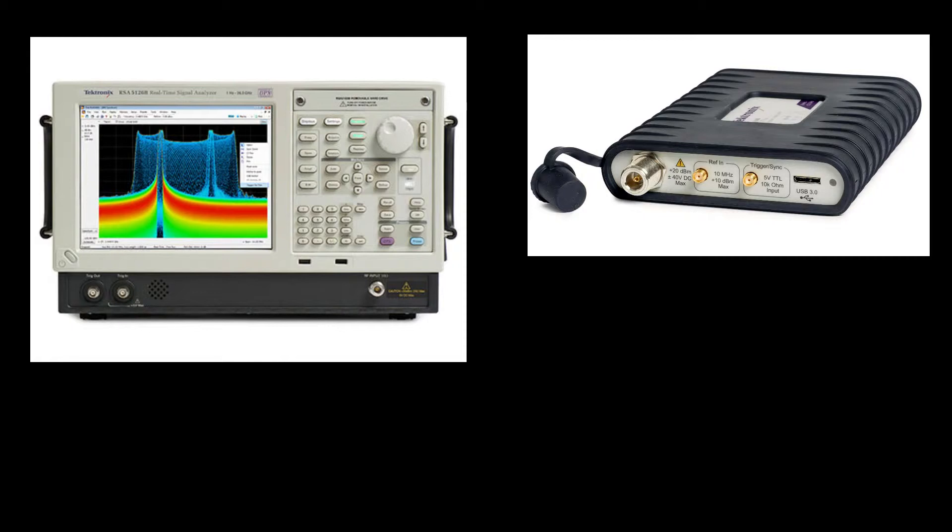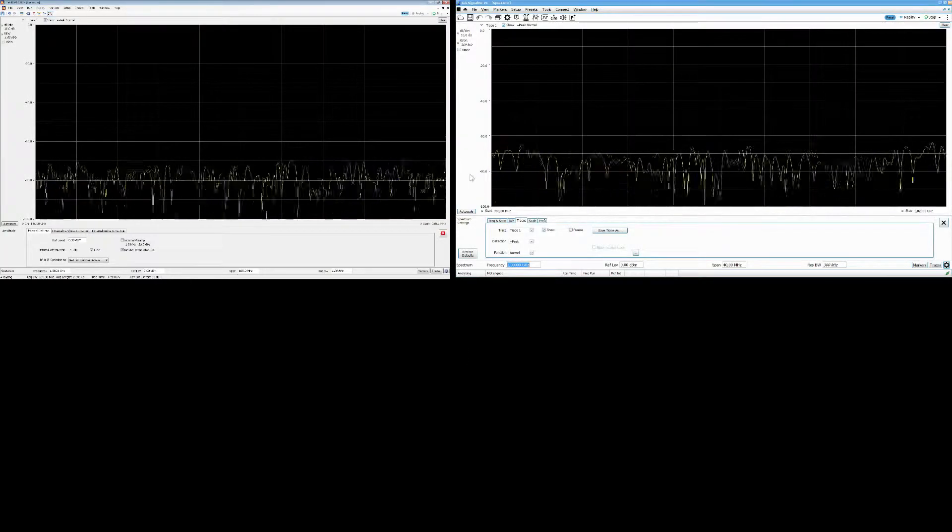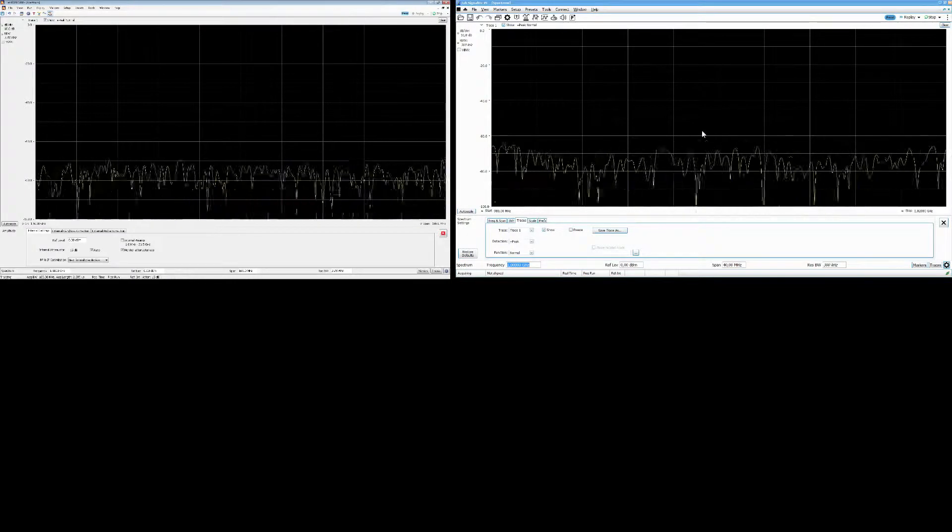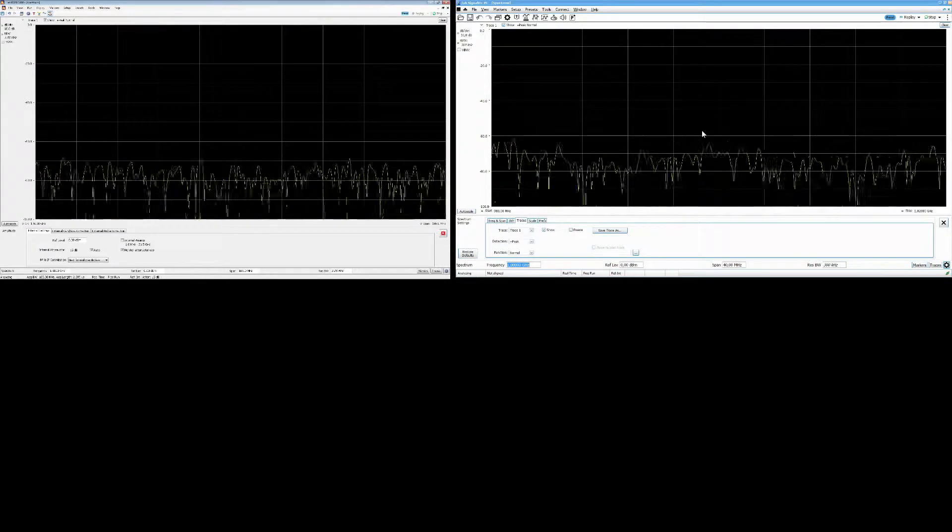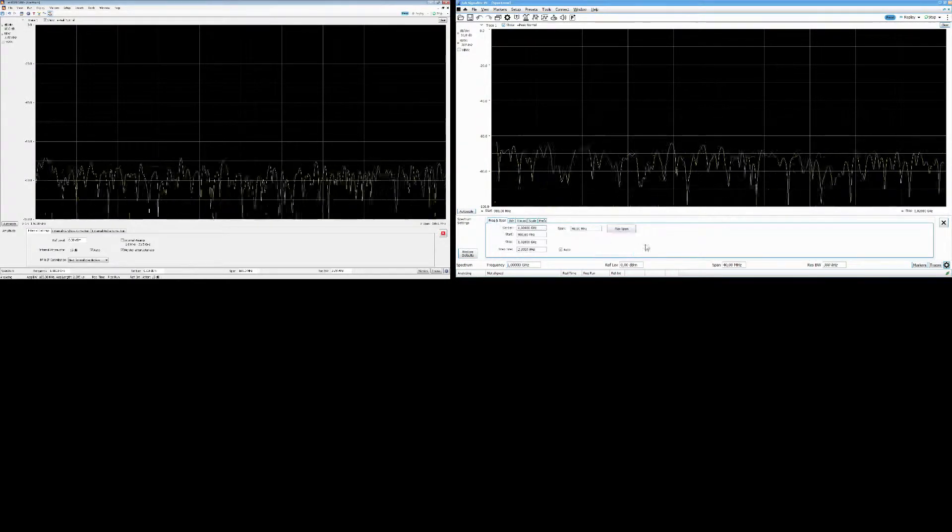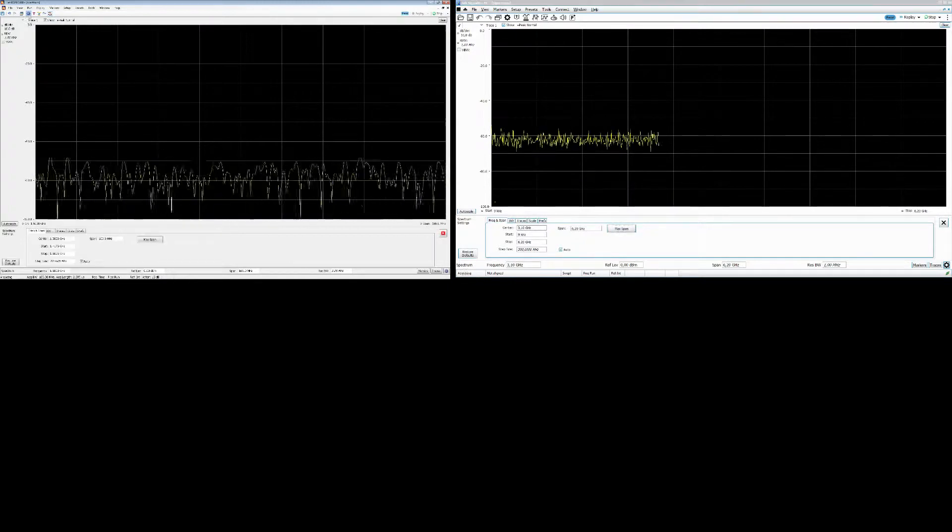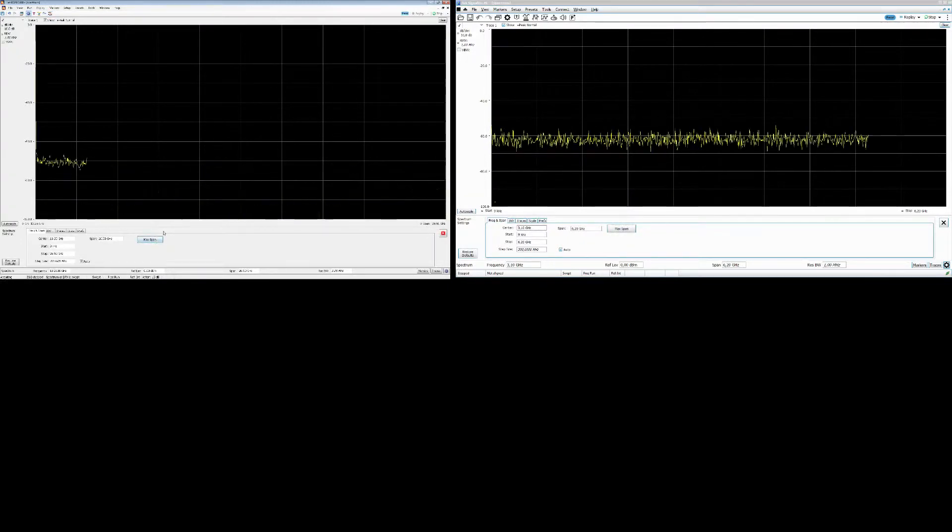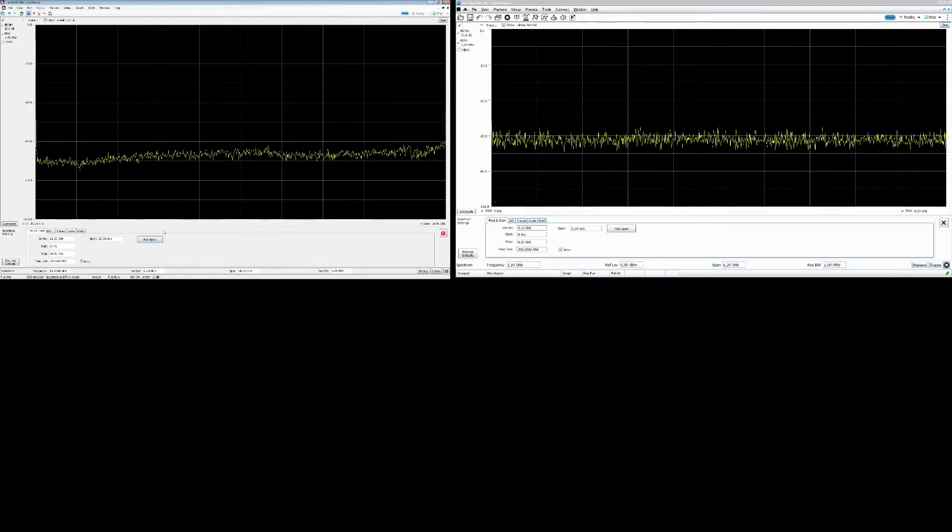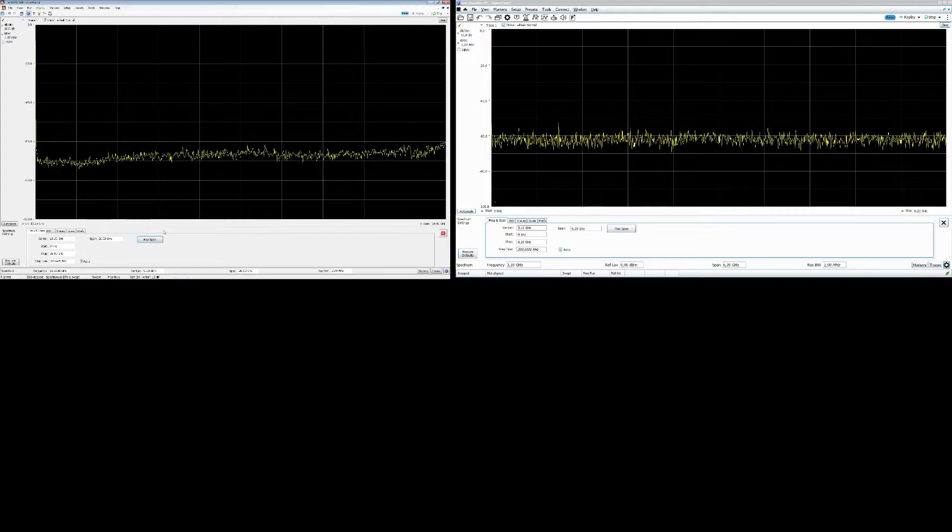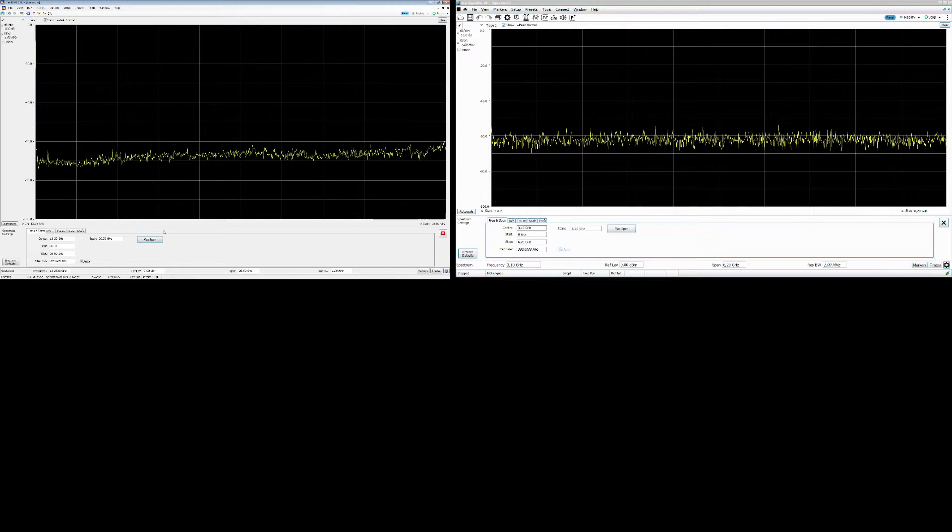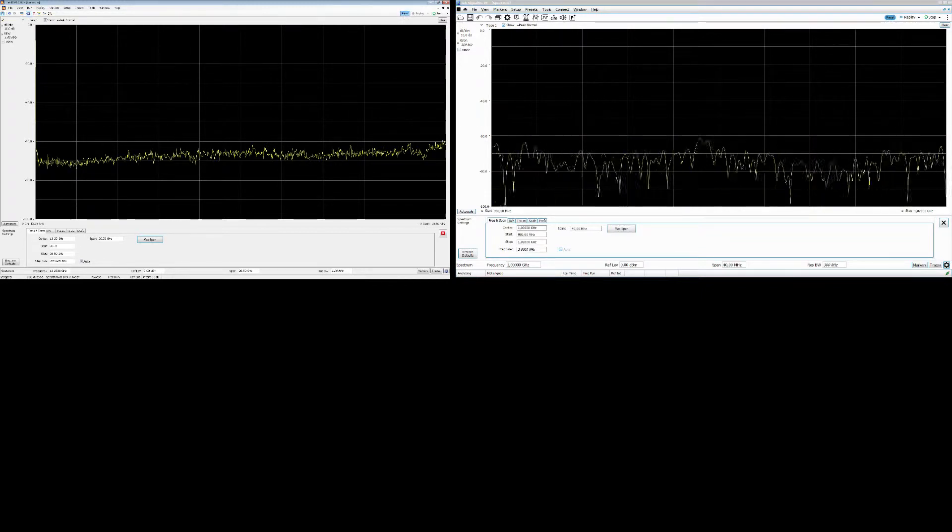Let's start by showing you this. Here is one thing that you can see. I can go in here, we have the frequency, I can set these guys to max span. The first thing you can see is the difference in the frequency coverage or frequency range. One goes from 1 Hertz more or less up to 26.5 gig and the USB from 9 kilohertz to 6.2 gig.